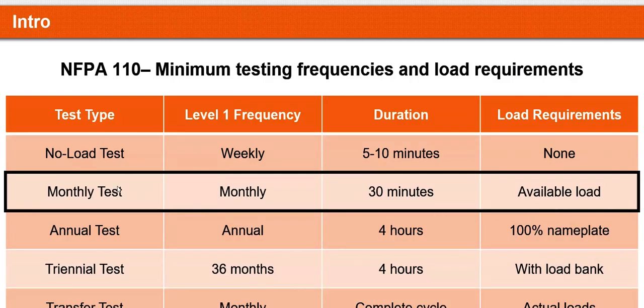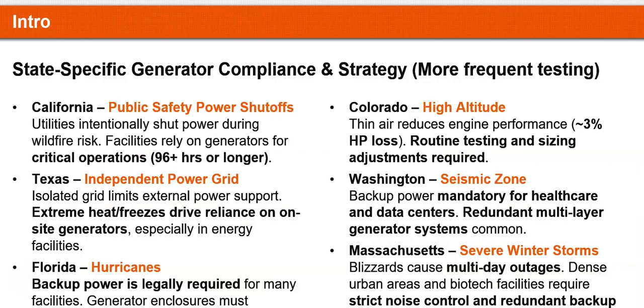And you may think, well, even if it's just the minimum, who cares? They just cover their ears for 30 minutes. What's the worst that could happen? Well, in many jurisdictions such as California, Texas, Florida, because of obvious reasons, whether you're in a hurricane area or you have harsh environments such as yours with a lot of freezing temperatures, if you lose power, you want to make sure that those backup generators kick in. A lot of these units are tested up to twice a week for half an hour.